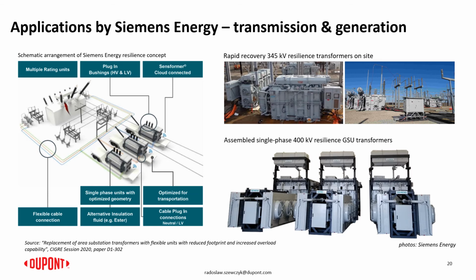And in the top picture, we can see those actual 100 MVA units installed in the substation. So because of the reduced size and weight and modular construction of those transformers, it was possible to place them quickly in the substation, although there was no specific base prepared for those transformers. There was no concrete pads prepared or the space for those transformers in the arrangement of the substation, but due to the reduced size as compared to the conventional 100 MVA units, it was possible to place them in the substation and connect with the plug-in bushings and cable connections to bypass the existing 300 MVA unit.